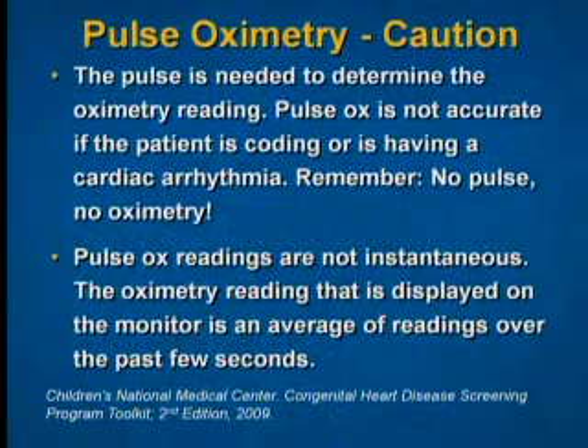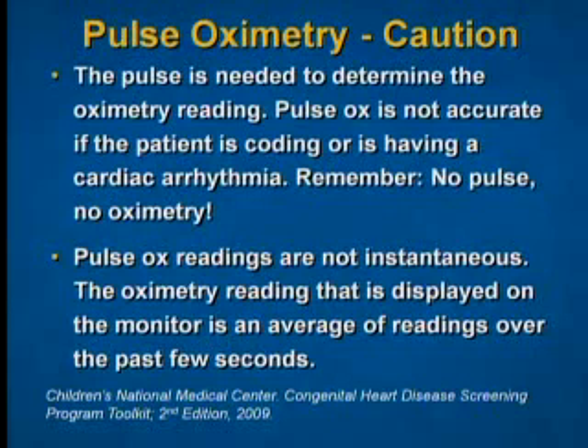And so they also just mentioned for the screener to be mindful that the pulse is needed to determine the oximetry reading. So the pulse ox is not accurate if the baby is coding or is having a cardiac arrhythmia. So remember, if there's no pulse, then there's no oximetry. And then it's also helpful to keep in mind that pulse ox readings are not instantaneous. So the oximetry reading that is displayed on the monitor is an average of readings over the past few seconds.